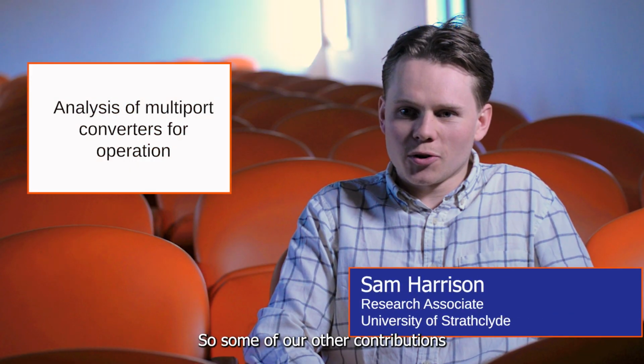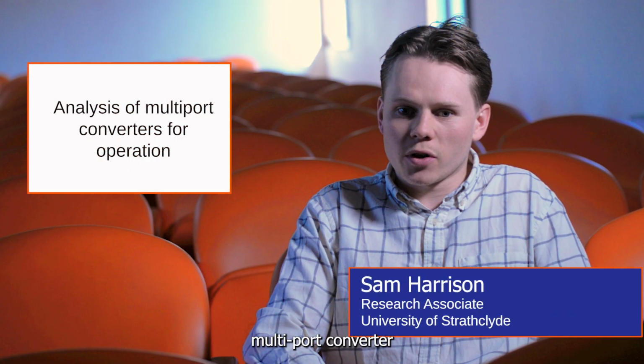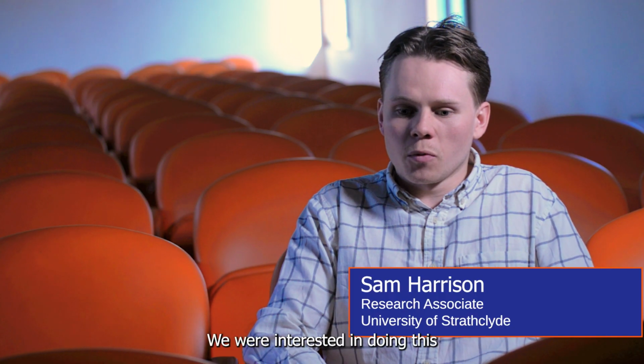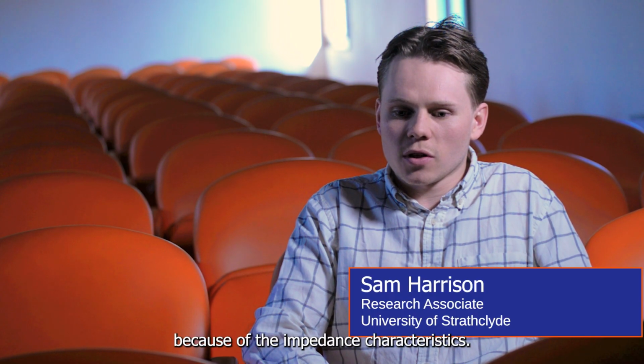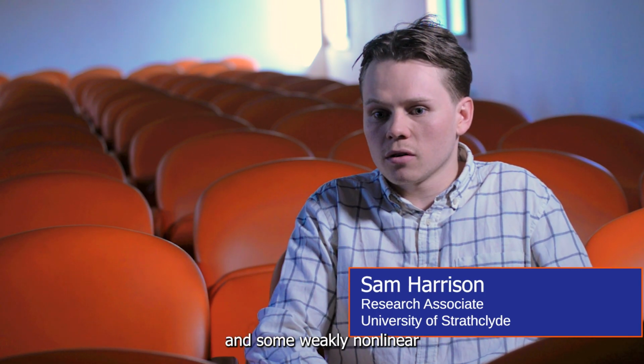Some of our other contributions for the medium voltage multiport converter involved trying to enable it to better support the distribution network. We were interested in doing this using grid forming converter control strategies. We were aware of some complications associated with implementing grid forming control in distribution networks because of the impedance characteristics, so we explored conventional grid formers and some weakly nonlinear grid forming control types. We identified their strengths and weaknesses and tried to explore ways to mitigate those issues.